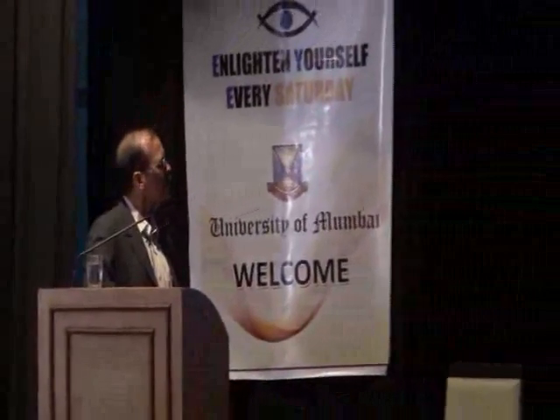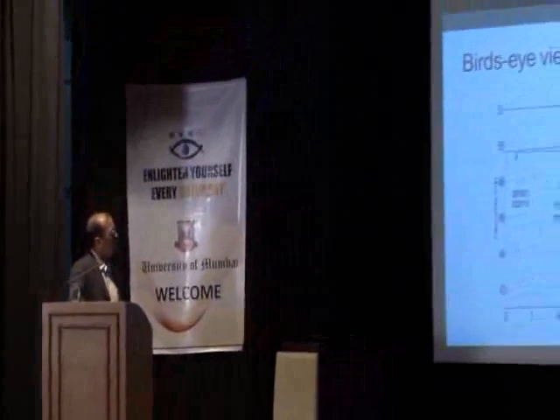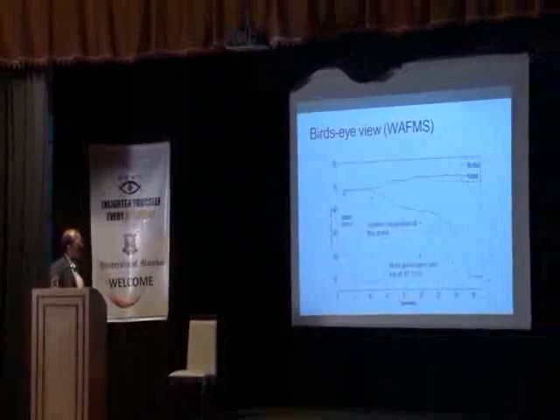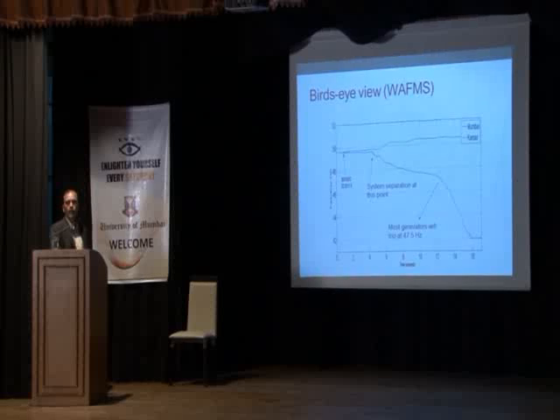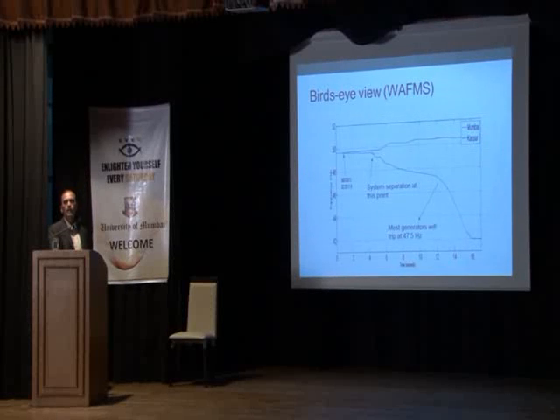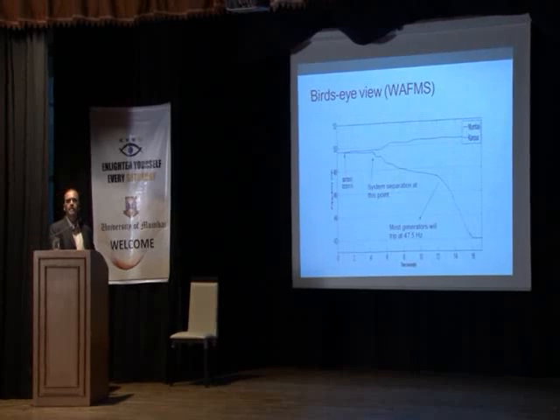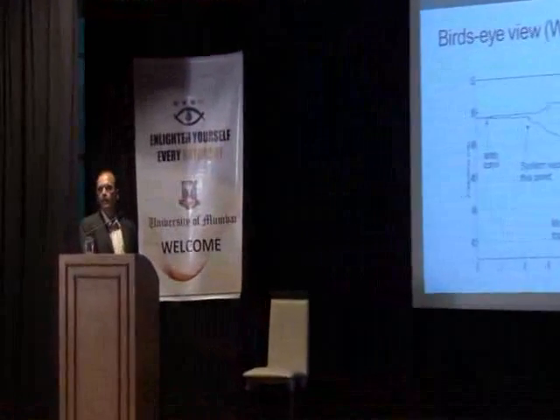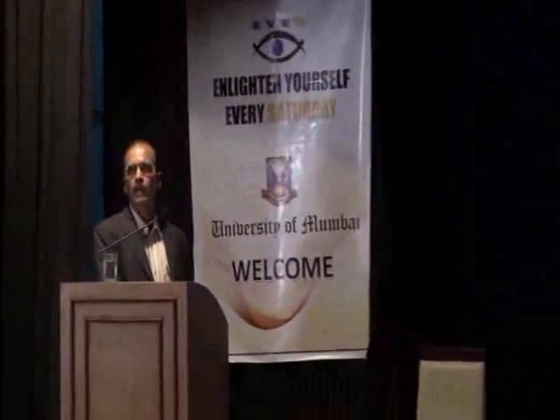In a nutshell, separation started 2 seconds from the disaster point. Later the generators tripped, meaning they shut down. This is the lower part of the graph; the upper part is the Mumbai-related subgrid, which continued to operate, still around 50 in the frequency domain. The generation capacity came down to a lower value, and then finally they all shut down here. The blackout took place. In layperson's terms, frequencies started to deviate between different parts of the grid, automatic shutdown mechanisms took over, closed the generators, and the rest is history.